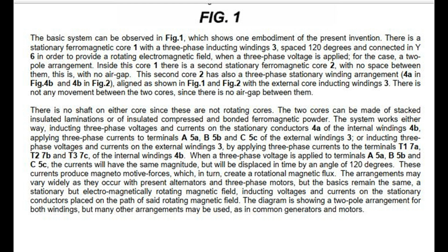The two cores can be made of stacked insulated laminations or of insulated compressed and bonded ferromagnetic powder. The system works either way, inducting three-phase voltages and currents on the stationary conductors 4A of the internal windings 4B, applying three-phase currents to terminals A5A, B5B and C5C of the external windings 3, or inducting three-phase voltages and currents on the external windings 3, by applying three-phase currents to the terminals T1 7a, T2 7b and T3 7c, of the internal windings 4B.